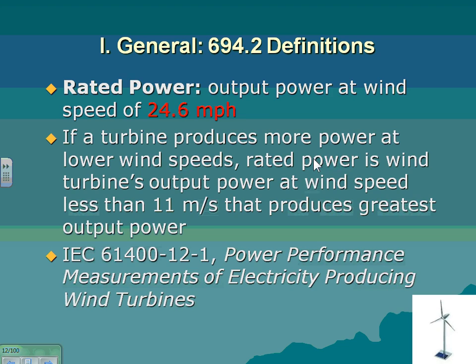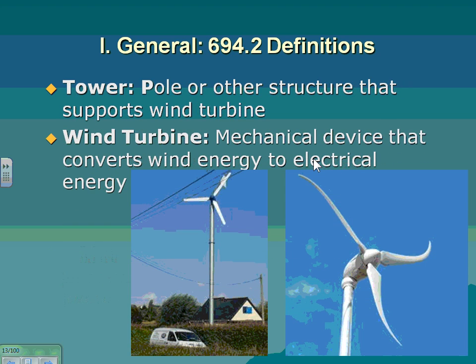So I thought I'd go through it very quickly. It talks about the tower and the turbine and what they do, the output circuit that we talked about, the equipment. This is very important. This is the article that I told you guys about. Every time you bring a power system into a building, you have to go to this 705. Long story short, you have to identify all sources of power at the service disconnect of the building by a label.